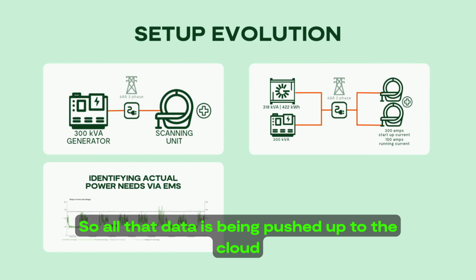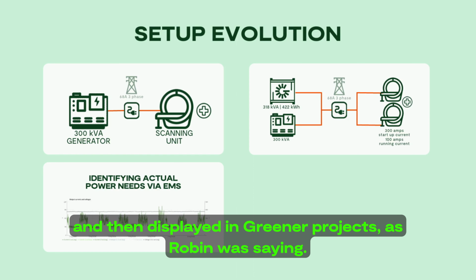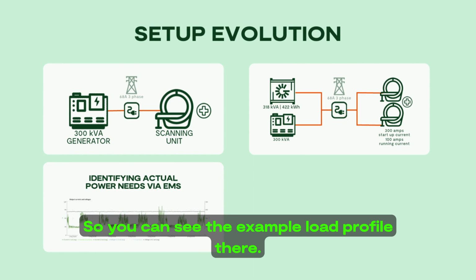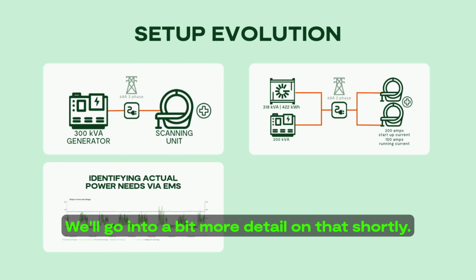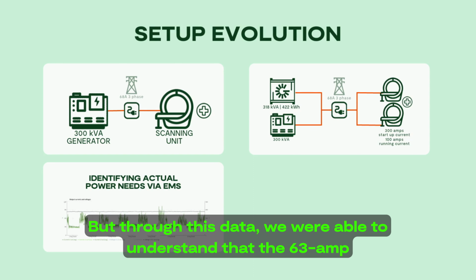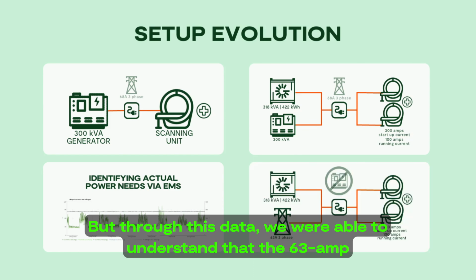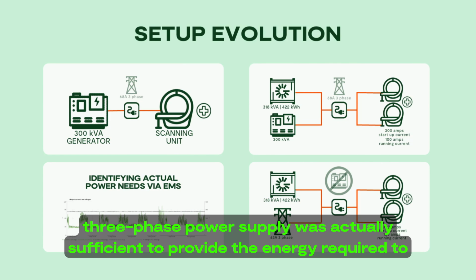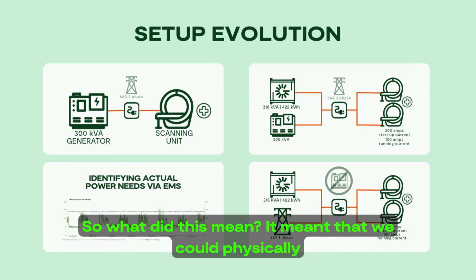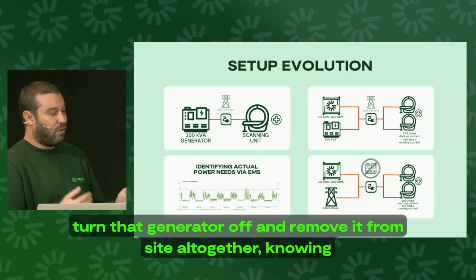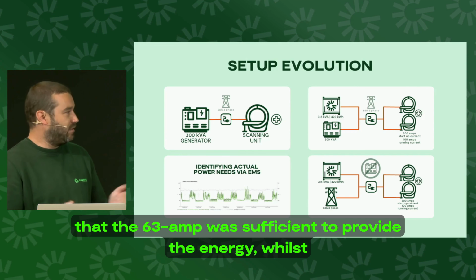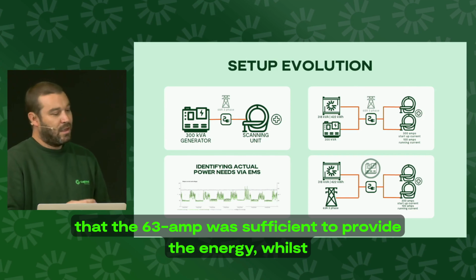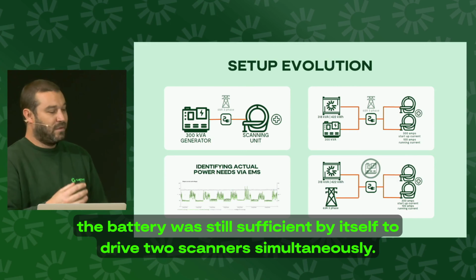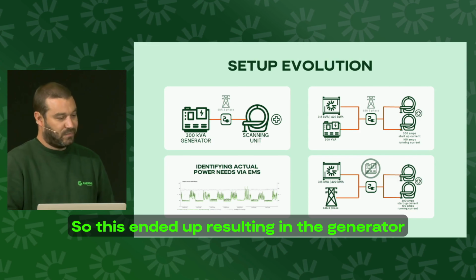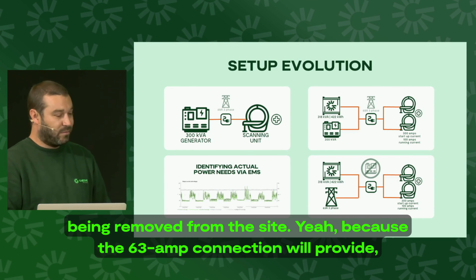But also through the installation of the battery, we start collecting data. All that data is being pushed up to the cloud and then displayed in Greener Projects, as Robin was saying. So you can see the example load profile there. We'll go into a bit more detail on that shortly. But through this data, we were able to understand that the 63 amp three-phase power supply was actually sufficient to provide the energy required to run both scanners. So what did this mean? It meant that we could physically turn that generator off and remove it from site altogether, knowing that the 63 amp was sufficient to provide the energy, whilst the battery was still sufficient by itself to drive two scanners simultaneously. So this ended up resulting in the generator being removed from the site.